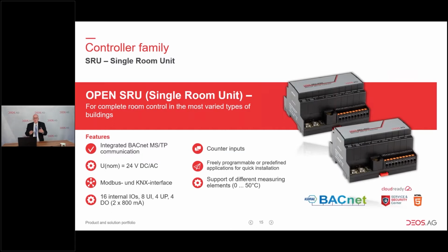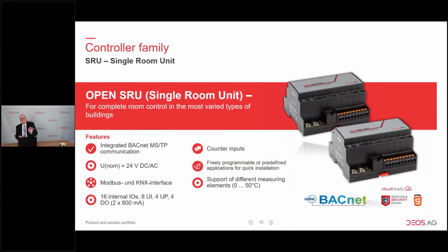From the perspective of room automation, DEOS also has a great solution: our SRU, meaning single room unit. The controller is freely programmable using the same engineering tool as our other controllers, so there's no extra tool to learn. With the same tool you use to control the main controller family, you also program the single room controller. We'll come back to this later. We also have many macros in our library for room automation to reduce programming and engineering time. The controller itself communicates over the BACnet MSTP protocol.